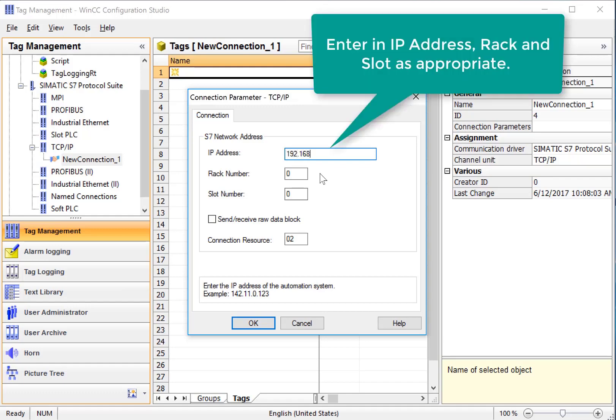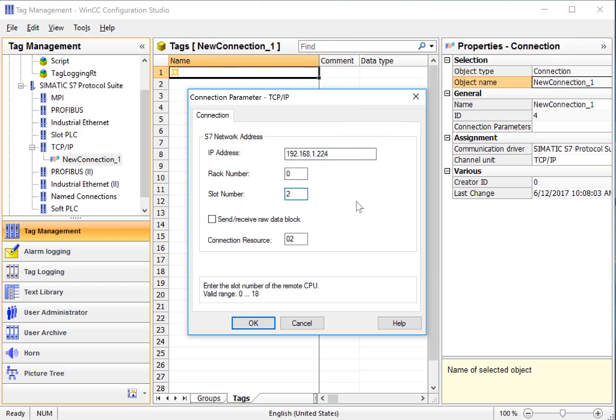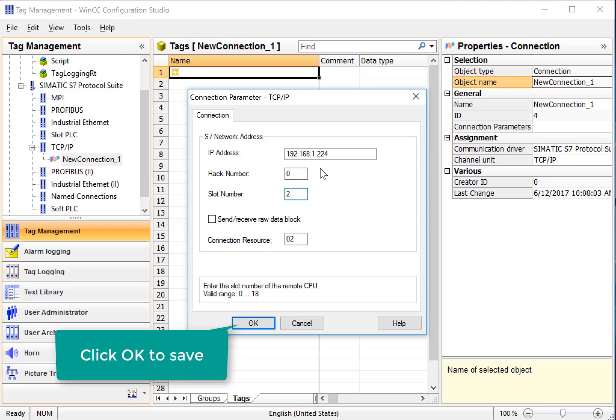I'll add an IP address and give it the correct rack and slot number. This is going to be the IP address of the communications processor on your PLC and the rack and slot of the communications processor. Then I'll just choose OK.